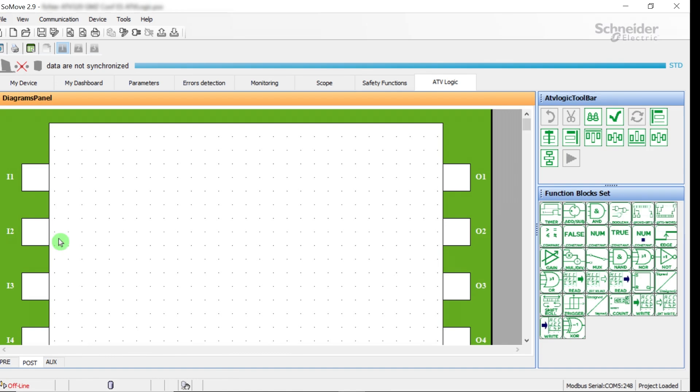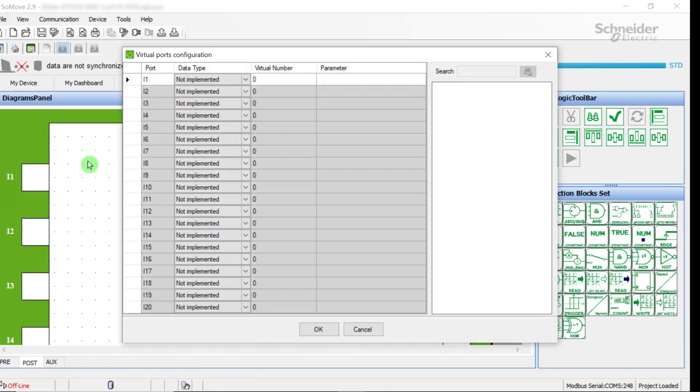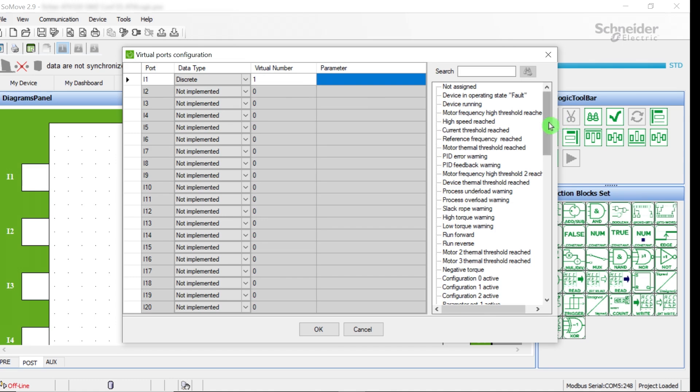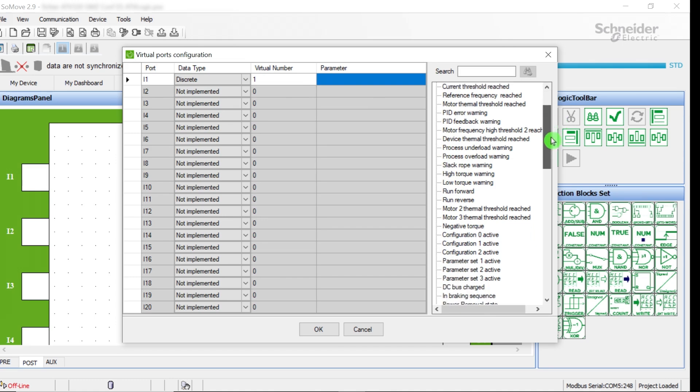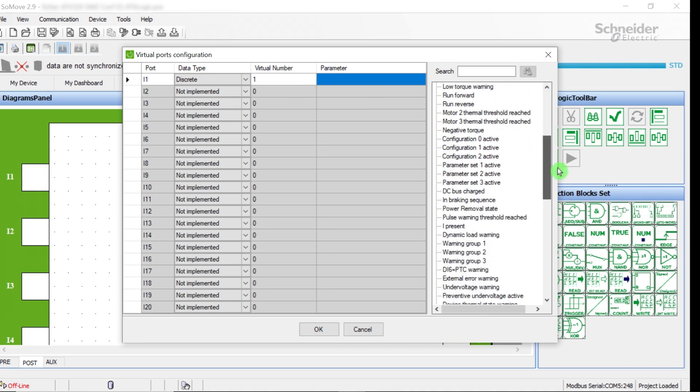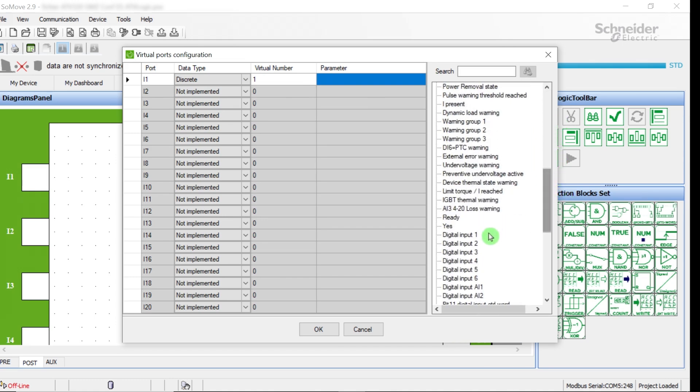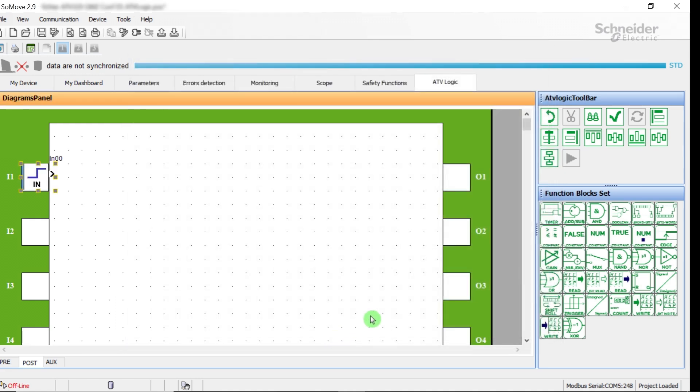Configure a logic input of ATV Logic Task to a hardware logic input. Double-click on I1 icon and configure the Virtual I1 to Hardware Digital Input 1 DI1 with 24 VCC. Choose Discrete in the list and Digital Input 1 in the right list which displays all the features that can be assigned to I1. Validate with the OK button. DI1 will decrease the counter value from the preset value to 0.